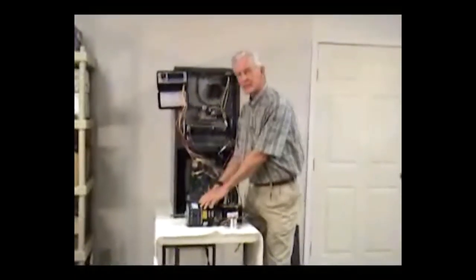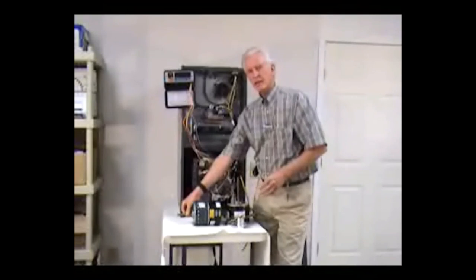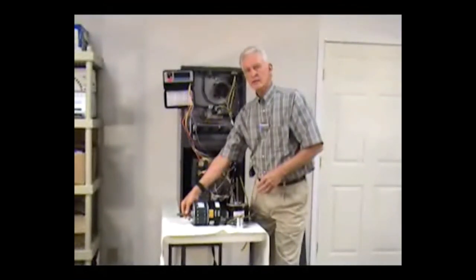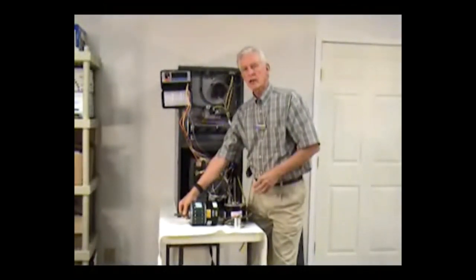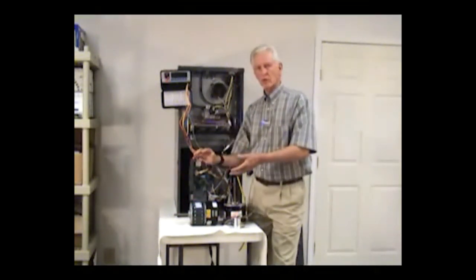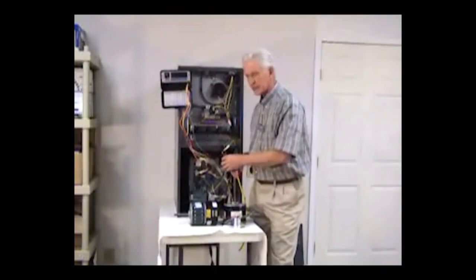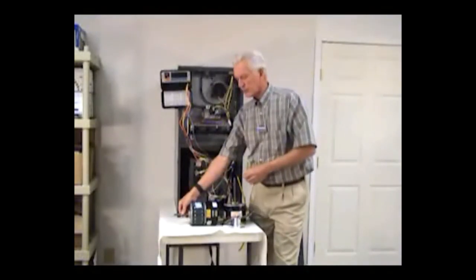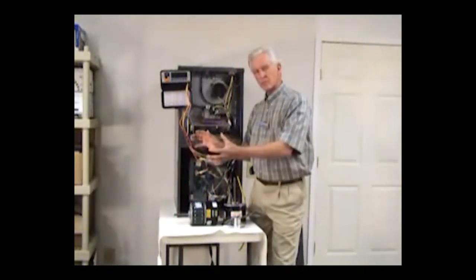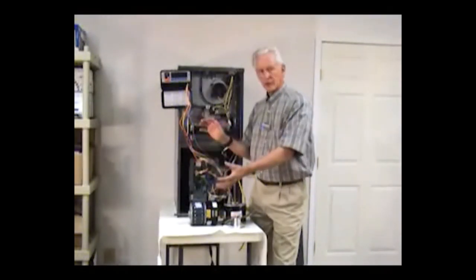from a split capacitor motor versus the ECM motors, is that on startup, the motors will do what is sometimes called hunt or hunting, and the motor will actually vibrate and make a small bumping sound where you can actually see the blower wheel. If you take the cover off and look inside, you'll see the motor actually rotate back and forth. In this particular case, I'm moving the shaft back and forth. It will take the blower housing and move it back and forth like this. Finding the direction that it needs to turn in is what it's doing.